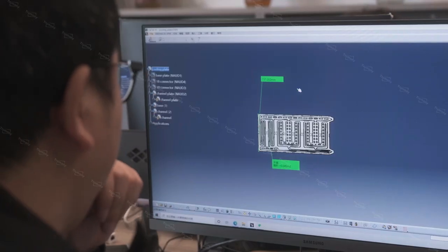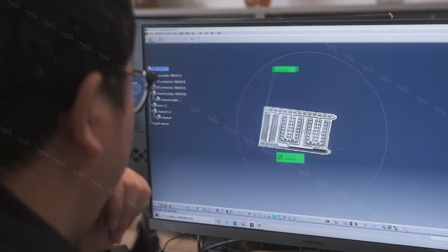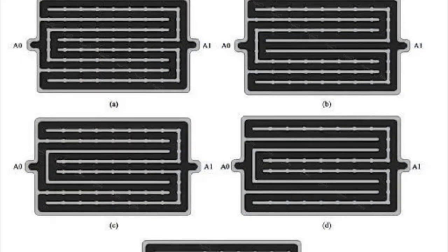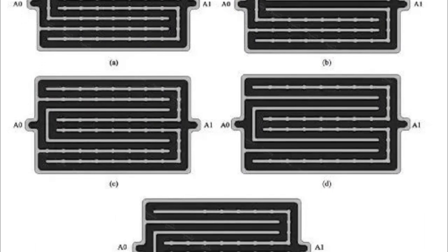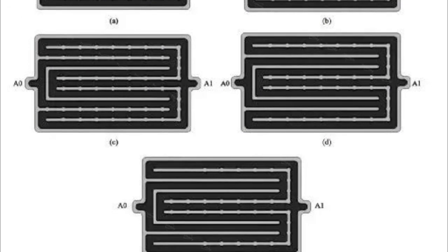In general, the heating power of the battery when discharging is greater than the heating power when charging. Therefore, it is sufficient to test the thermal power of the battery module at the 1C discharge rate.